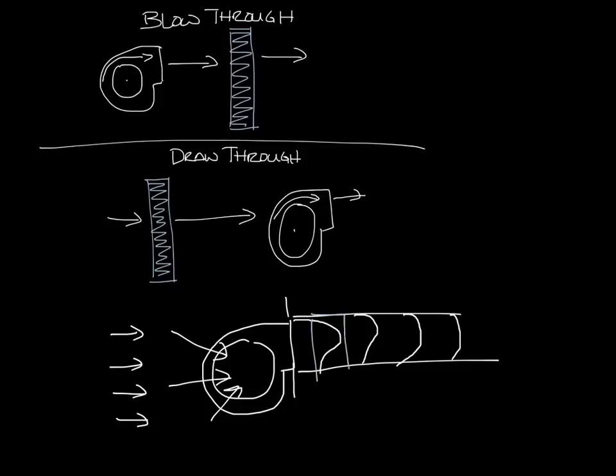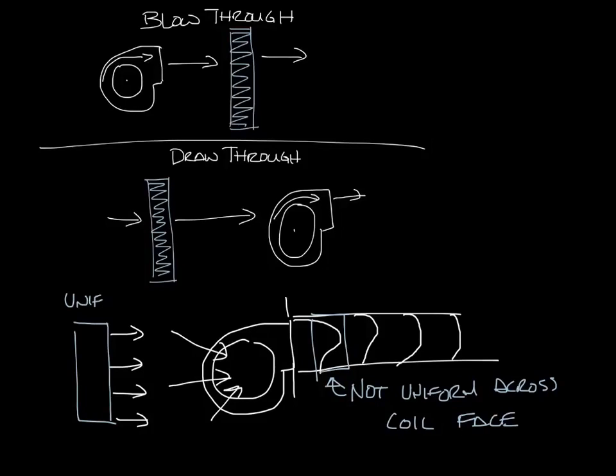So if you were to put a water coil right here in this section of a blower in a blow-through configuration, you may not get uniform flow across the coil face, whereas if you put a water coil back here, you should get pretty uniform flow across the face of the coil. So when you look at how the air is moving, if you need more even flow, you'll want to have a draw-through configuration. If you use blow-through in these situations, you may need to put the coil further away from the fan to allow for the air to become more uniform, and then that'll add length to the unit, which will add cost and take up more space. For this reason, most air handlers are draw-through.